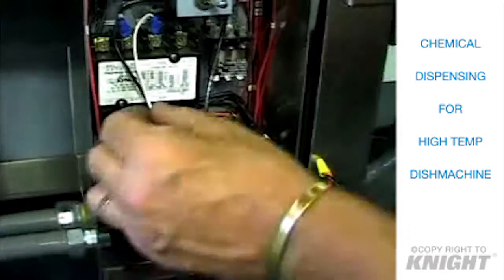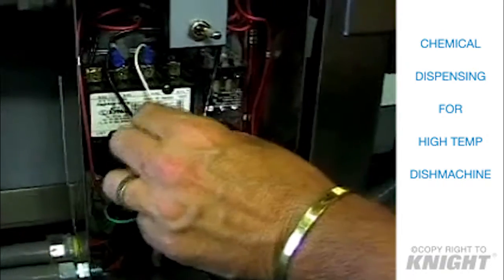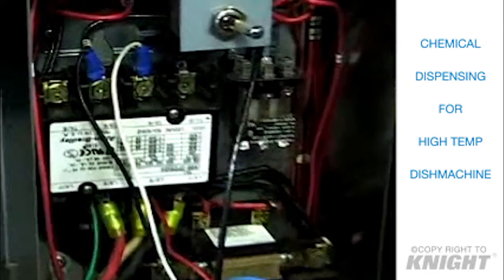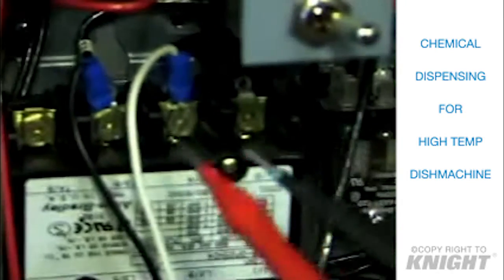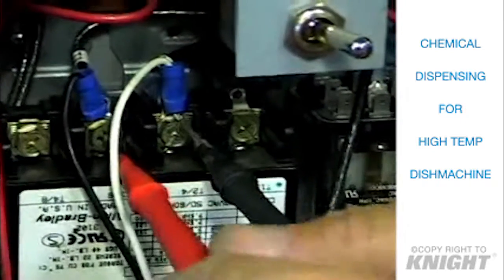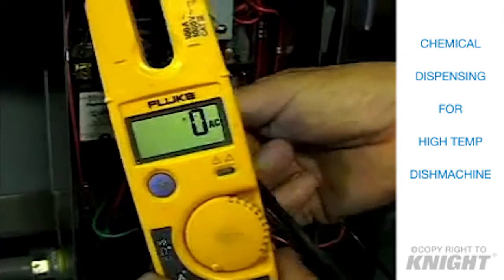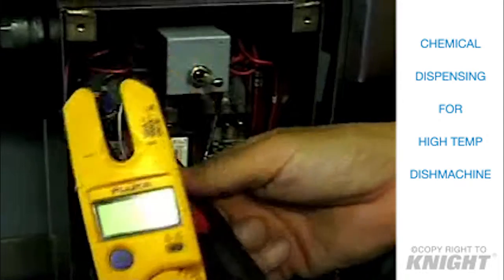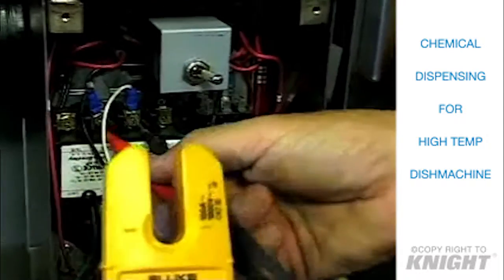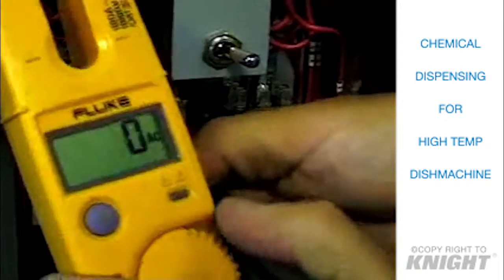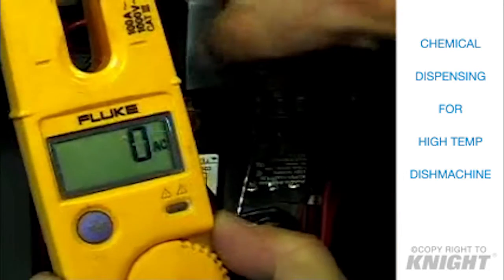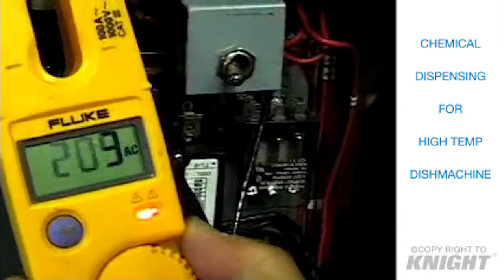I also have a black and white wire hooked up to the secondary side of the magnetic contactor, and you'll see that if I test this, there is no power. But if I just leave those leads on there for a moment, if I can just hang on to this so I can keep it in the view of the camera and flip the switch on, you'll see that this is going to come on now.